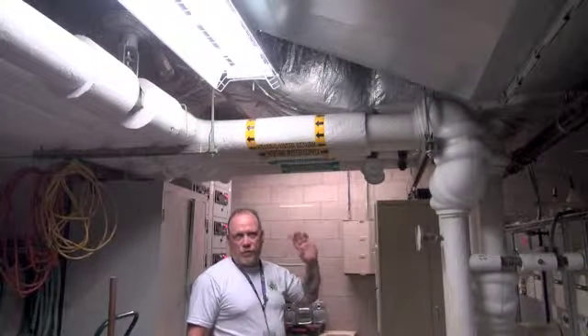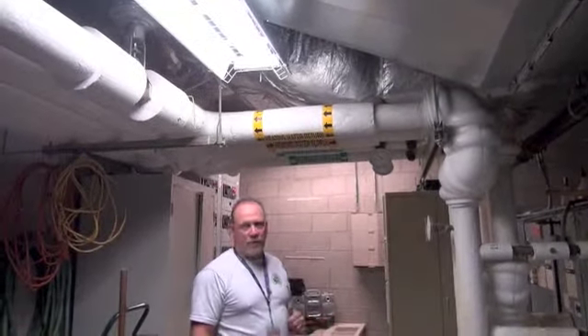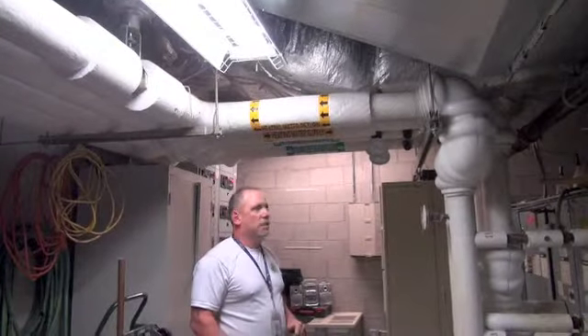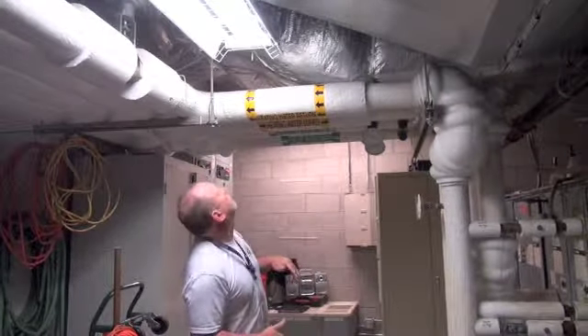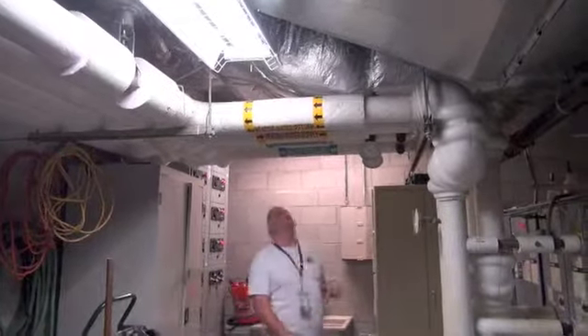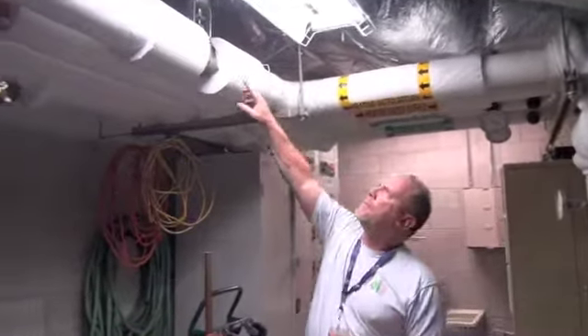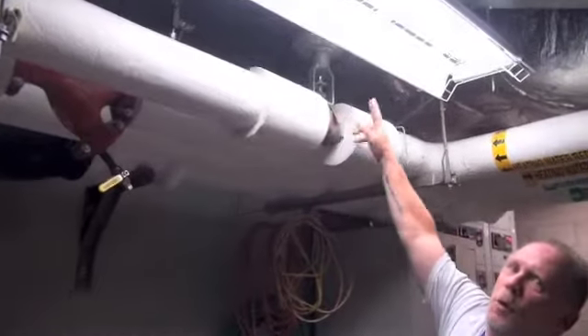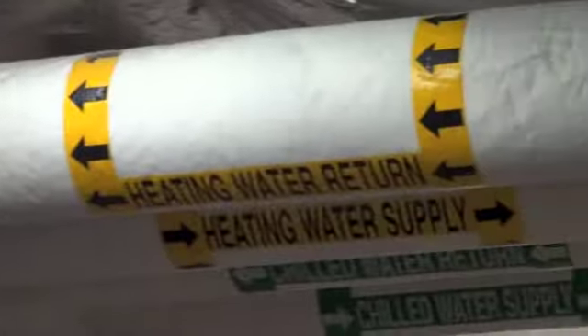Basically, everything's worked off zone temperature. We have a zone set point of 70 degrees, 75 degrees. There's a heating valve, cooling valve right here. This will modulate, open or close to allow hot water or cold water into the coil. The fan blows cold or heat, cooling into the space, and as that temperature is satisfied, that'll back down and close off. Basically the same thing for heating, which is a larger valve. It's back further. You see it back there.